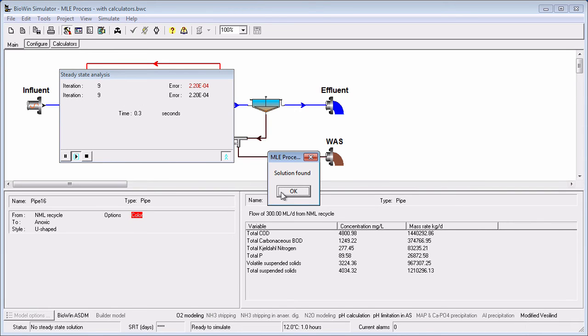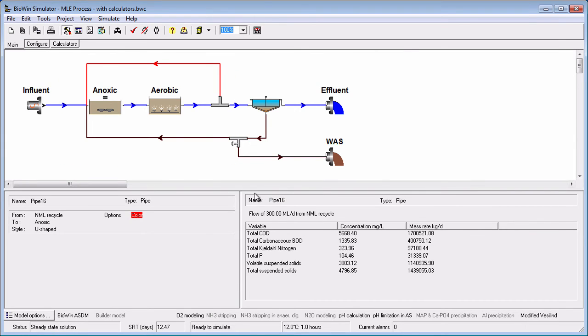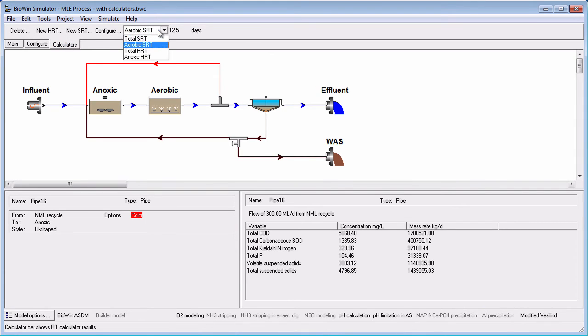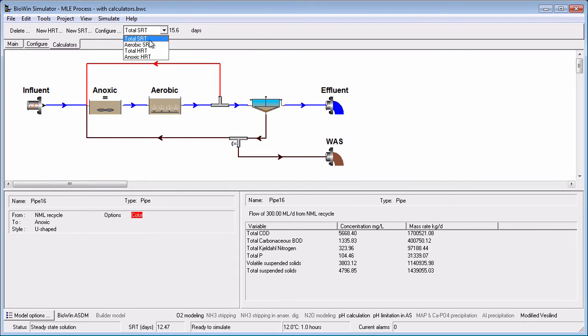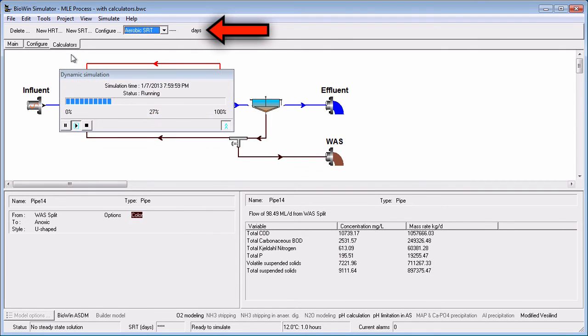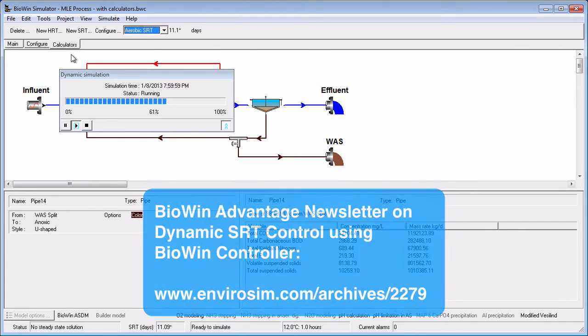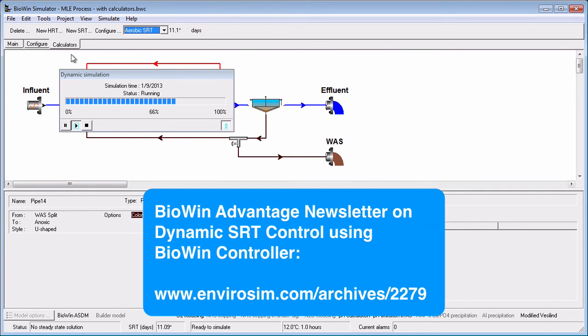Note that if we're solving for something like an aerobic or anoxic SRT, then if we've defined the total SRT, that value also will be updated. Note that if we run a dynamic simulation, the steady state waste flow will be applied, and the SRT may vary around the target steady state value accordingly. To achieve a constant SRT by continually varying the waste flow, we would need to use the BioWin controller.